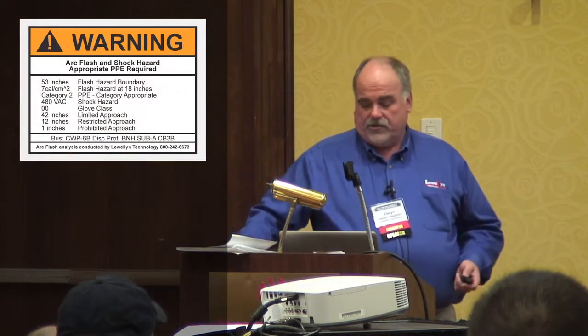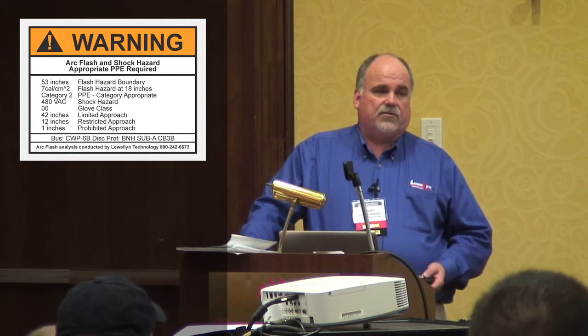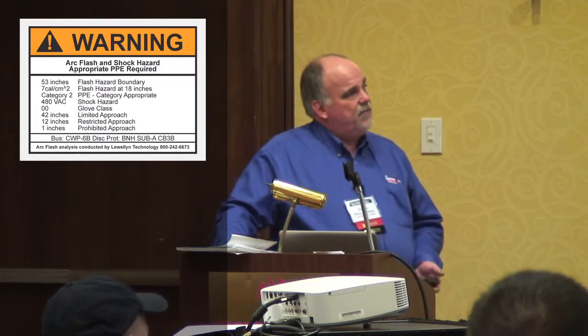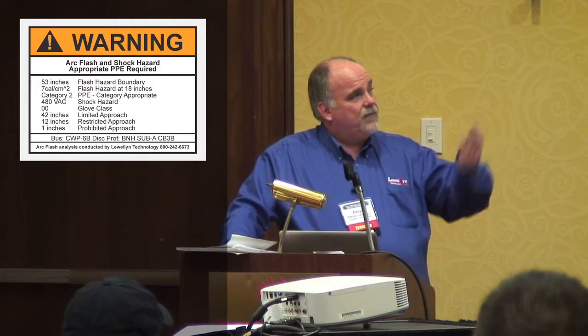This is what your labels might look like. This also has shock protection on it, with shock hazard information, not just arc flash. This arc flash boundary is 53 inches, which means if that panel is open and you can see the shiny parts, anyone within 53 inches of those exposed shiny parts has to be wearing Category 2 clothing, which is 7 calories per square centimeter. That's the energy on this particular panel.